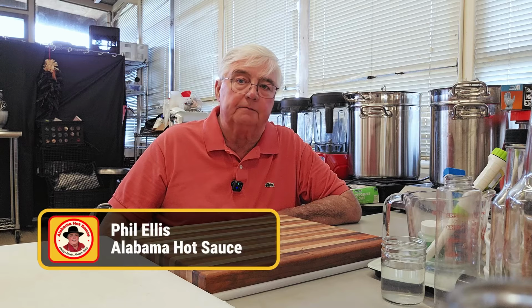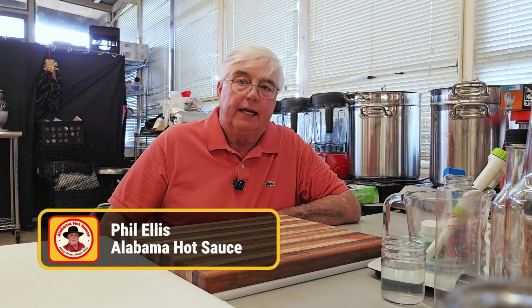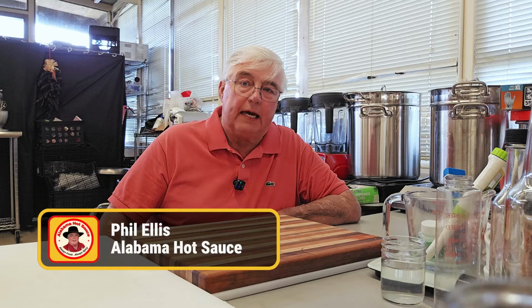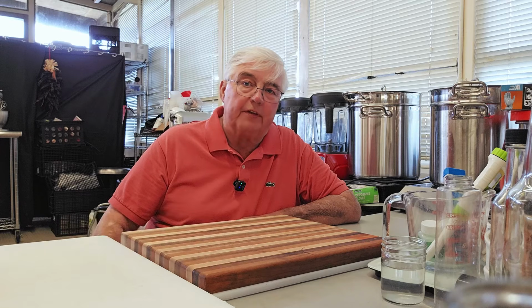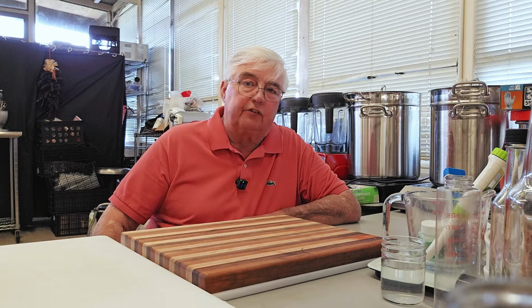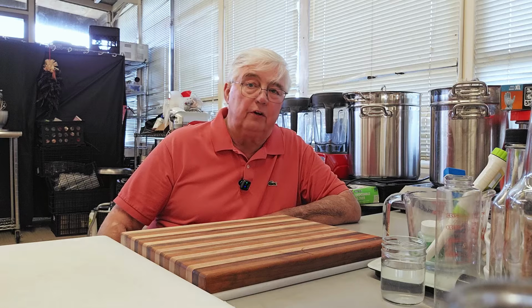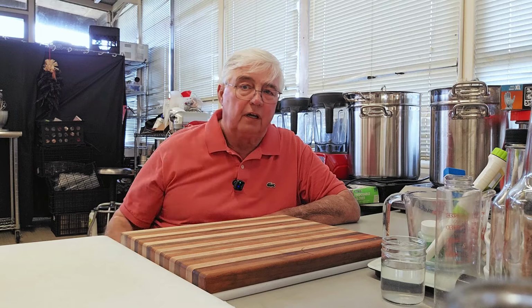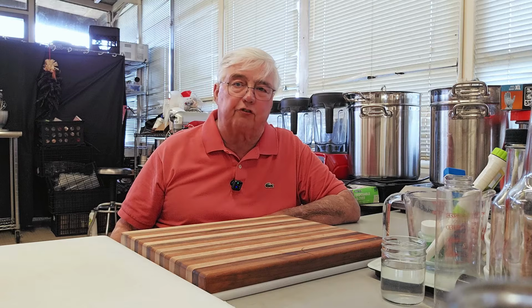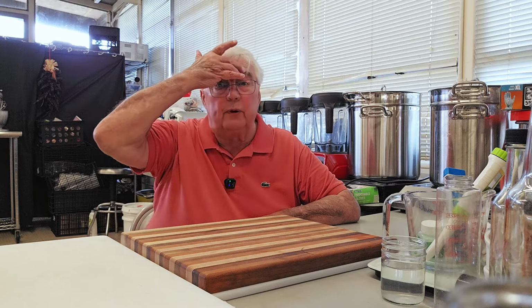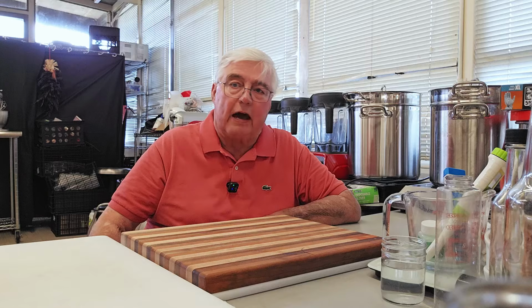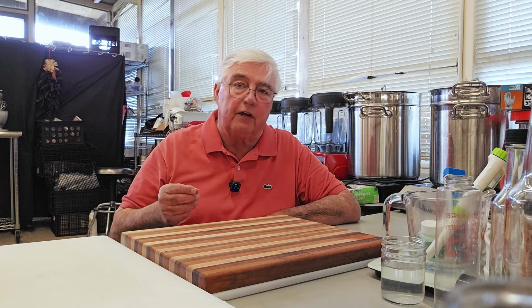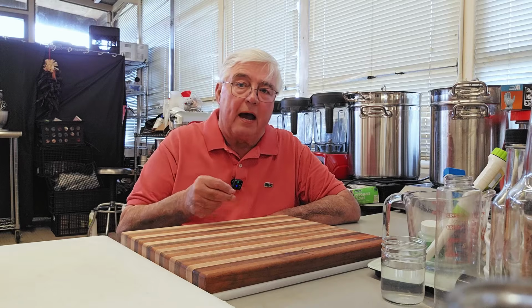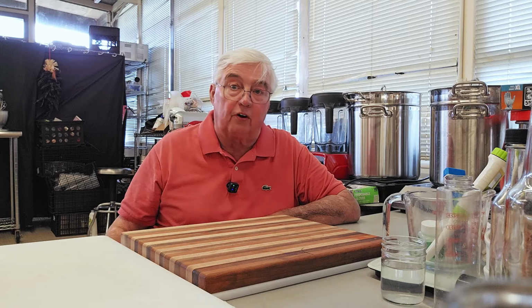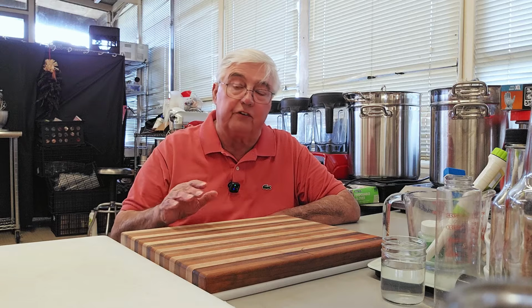When I look on social media and in my emails and anywhere else where the subject of pH meters comes up, the most common thing I find is people saying, it is so aggravating to calibrate my meter. I've quit using my meter because it's difficult to calibrate. I'm now using test strips. There seems to be a tremendous amount of angst when it comes to calibrating these meters. So what I wanted to do in this video is show you really how simple it is to calibrate your pH meter. Not your particular brand or my particular brand, but every pH meter. They all work, with a few small differences, the same way.